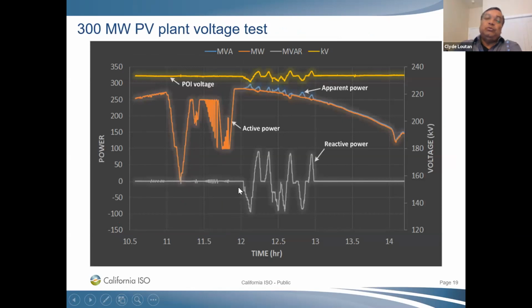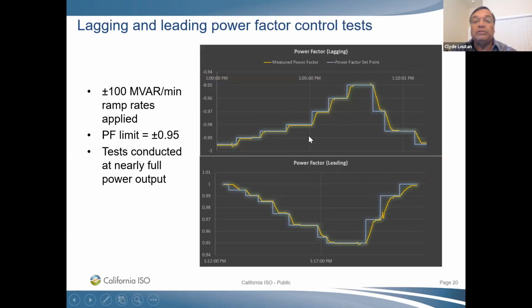This plot here shows you one thing: the active power control and the reactive power control are independent. At the first part of this plot, you can see this orange curve here. We moved this unit quite a bit from about 260 megawatts to 0 and back and forth. And if you look at this yellow curve, which is your voltage on the high side of your step up transformer, you can see how stable the voltage was. Only when you move the megavar output do you see the voltage change. So the active power control and the reactive power control are independent. We saw that with the controls of this unit. So again, very encouraging response.